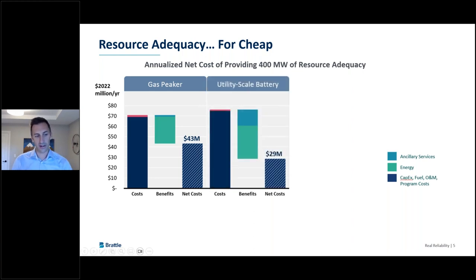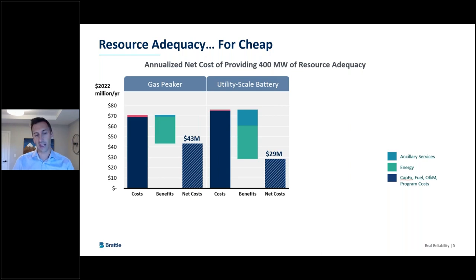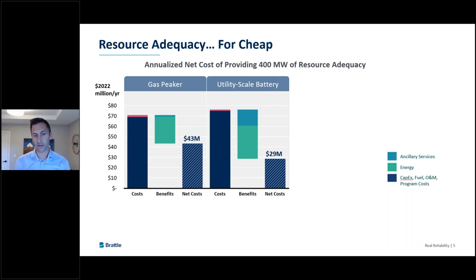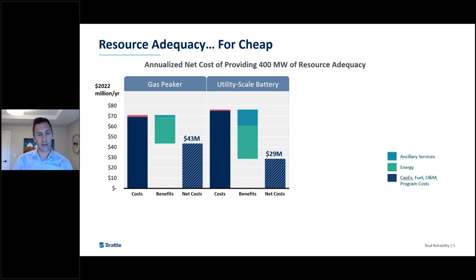For utility-scale batteries, the annualized cost of getting 400 megawatts of capacity value is similar to the peaker — between $70 and $80 million per year. In our base case, the utility-scale battery provided more energy and ancillary services benefits than the peaker, because the battery could operate more often and provide more benefits across more days of the year. So ultimately the economics of batteries look more attractive than the gas peaker, but you're still left with about $29 million in net costs to get 400 megawatts of resource adequacy.